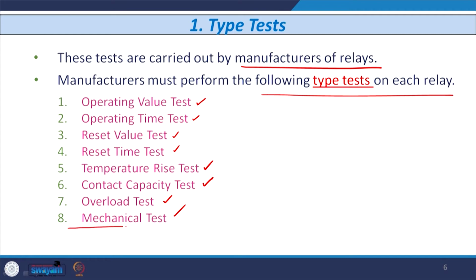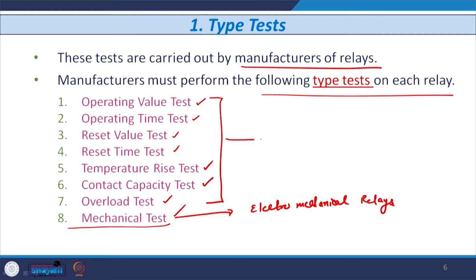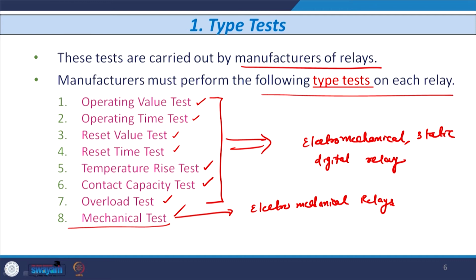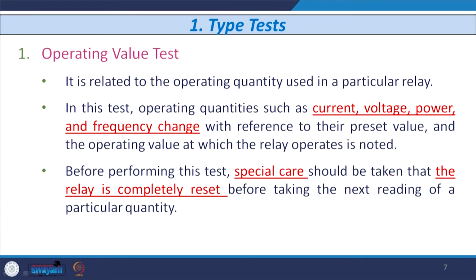This mechanical test is performed only on electromechanical relays, it is not performed on the next generation relays. So, this is only for electromechanical relays, whereas the rest of the tests are performed on electromechanical, static and digital relays. So, let us see these 8 tests one by one. Let us start with the operating value test. This is one of the type tests.